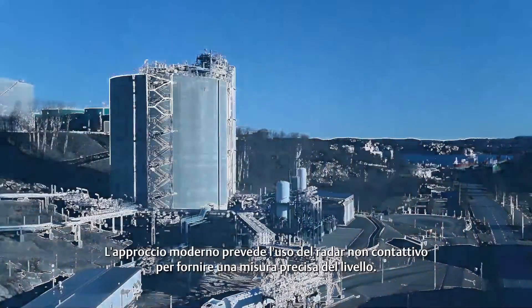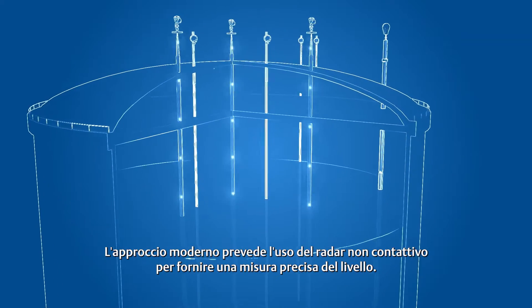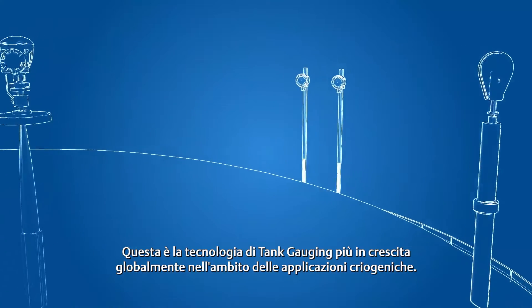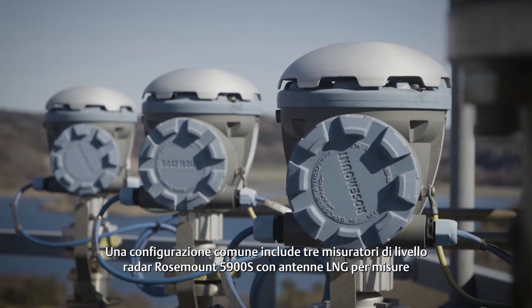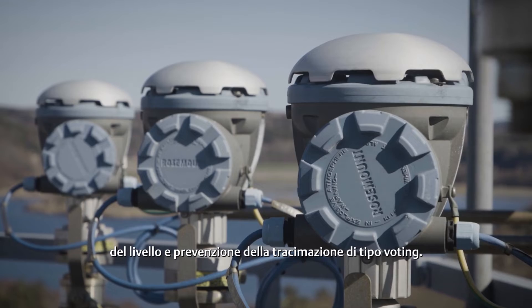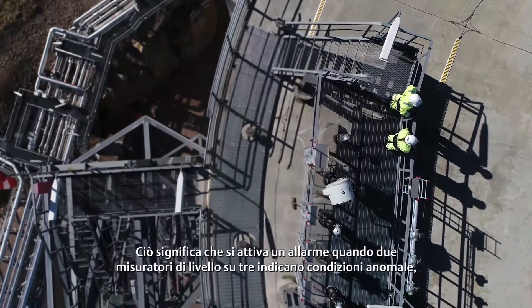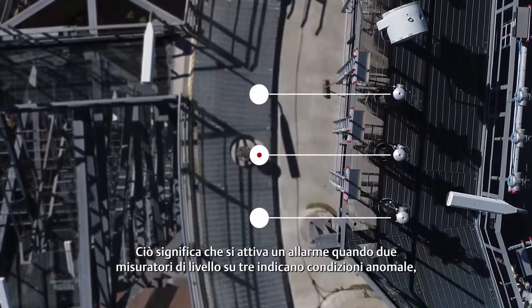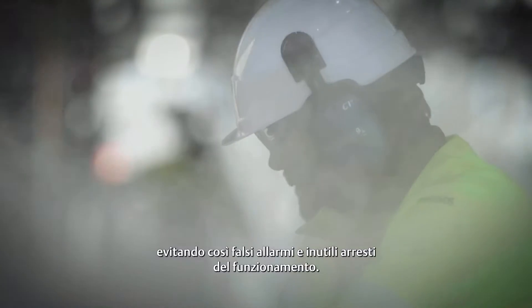The modern approach involves using non-contacting radar to provide precise level measurement — this is the fastest growing tank gauging technology across the world for cryogenic applications. A common set-up includes three Rosemount 5900S radar level gauges with LNG antennas for level measurements and voted overfill prevention, meaning an alarm is triggered when two out of three level gauges indicate abnormal conditions, thereby avoiding false alarms and unnecessary operation stops.